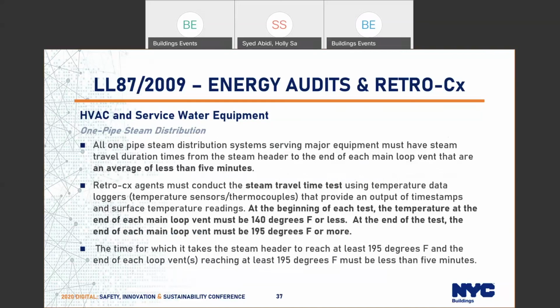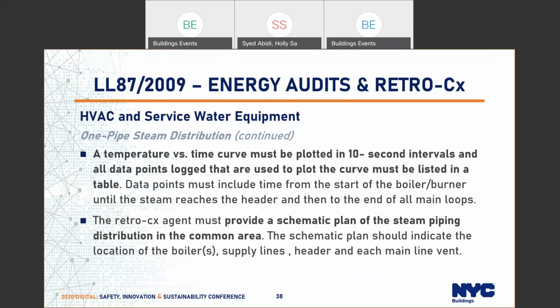There is a one-pipe steam distribution test that is now listed within the requirements of the rule amendment. The retro-commissioning agent must conduct the steam travel time test using temperature data loggers to satisfy the requirements and to ensure that the one-pipe steam is being distributed in a balanced manner.